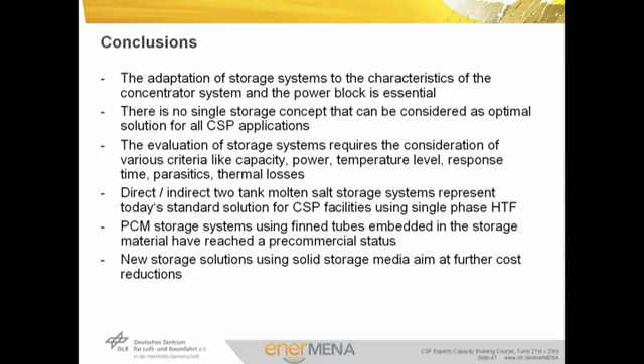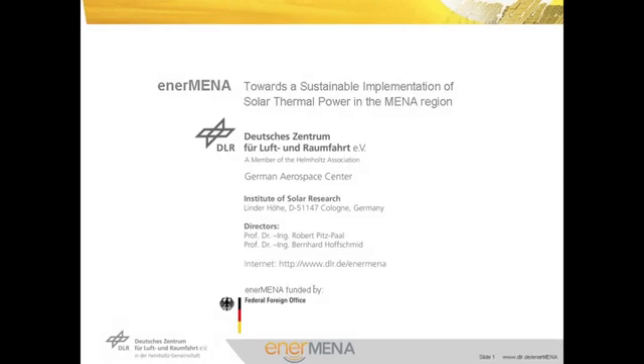Coming to the conclusions: the adaptation of storage systems to the characteristics of the concentrator system and the power block is essential. There is no single storage concept that can be considered an optimal solution for all CSP applications. The evaluation of storage systems requires the consideration of various criteria like capacity, power, temperature level, response time, parasitics, and thermal losses. Direct and indirect two-tank molten salt storage systems represent today's standard solution for CSP facilities using single-phase HTF. PCM storage systems using finned tubes embedded in the storage material have reached pre-commercial status. There are new storage solutions using solid storage media which aim at further cost reductions. We acknowledge the financial support of the enerMENA project by the German Federal Foreign Office.